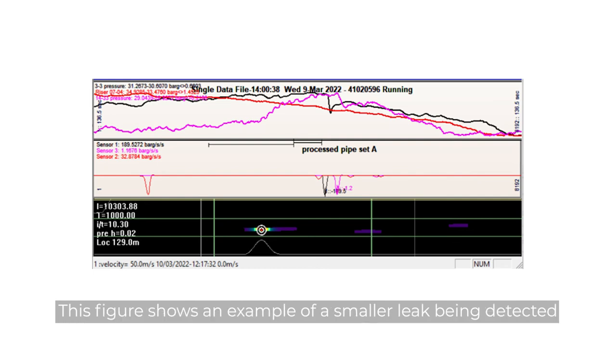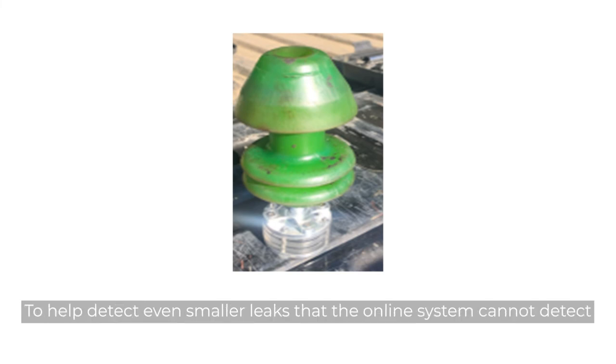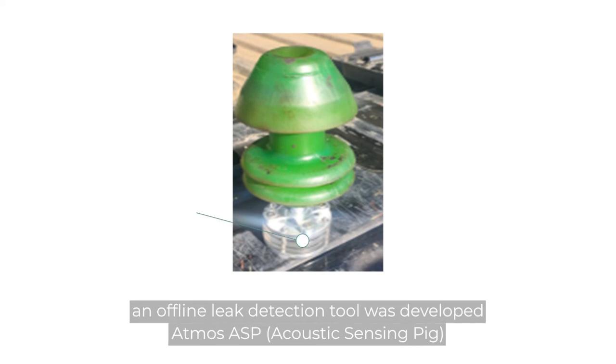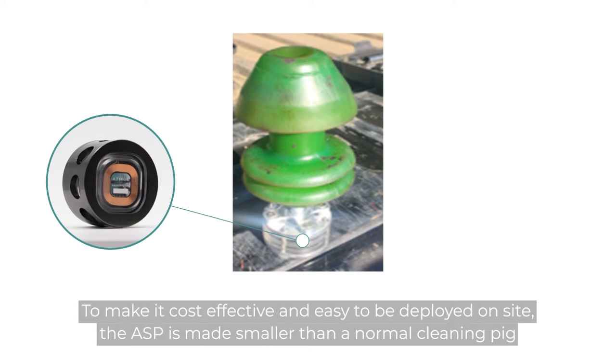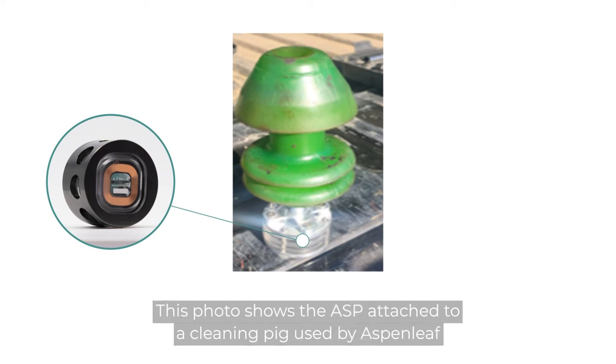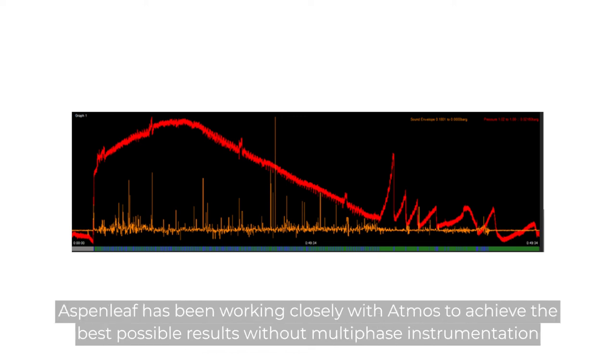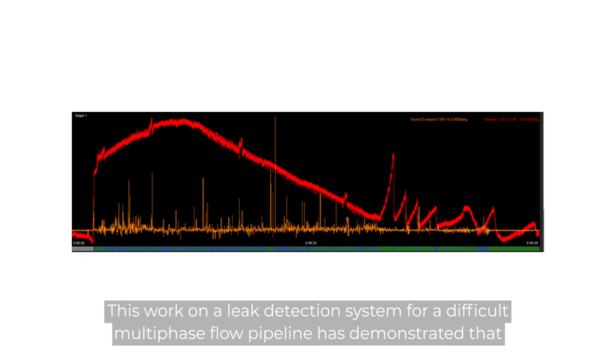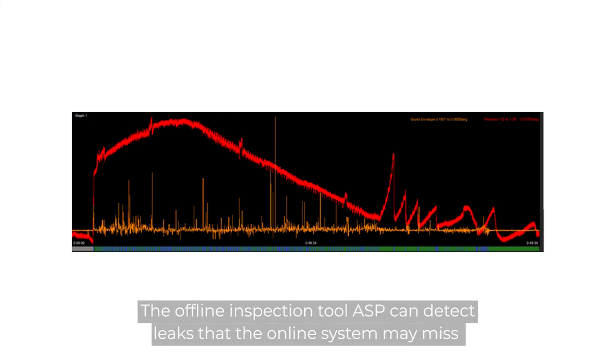For multi-phase pipelines, pigging is usually carried out regularly to clean the pipelines of debris and stagnant liquids. To help detect even smaller leaks that the online system cannot detect, an offline leak detection tool was developed: Atmos ASP, Acoustic Sensing Pig. To make it cost-effective and easy to deploy on-site, the ASP is made smaller than a normal cleaning pig. It can be attached to a cleaning pig before a routine pigging is carried out. This photo shows the ASP attached to a cleaning pig used by Aspen Leaf. This figure illustrates that no leak was detected in the section surveyed by the ASP. Aspen Leaf has been working closely with Atmos to achieve the best possible results without multi-phase instrumentation. This work has demonstrated that the real-time negative pressure wave system can detect leaks of a reasonable size for the river crossing section without false alarms, and the offline inspection tool ASP can detect leaks that the online system may miss.